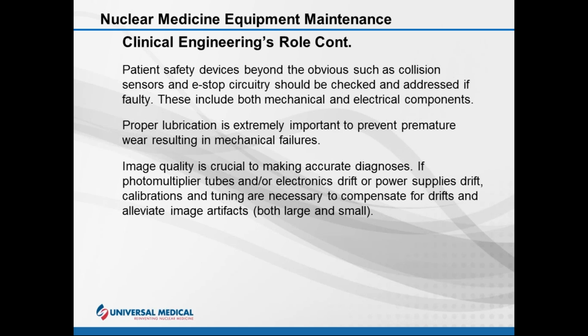And then also being aware of the mechanical and the electrical components. Lubrication. There are a lot of gears, as you know better than I. Make sure there is proper lubrication so that these function normally when the table is moving to do that total body scan that we're doing, or the SPECT is rotating around the patient. It's important to do lubrication, and not just lubricate on top of lubrication. The best approach I've heard, recommended by the engineers, is to remove all of the old lubrication, or as much as possible, and put on fresh, new lubrication or new grease.